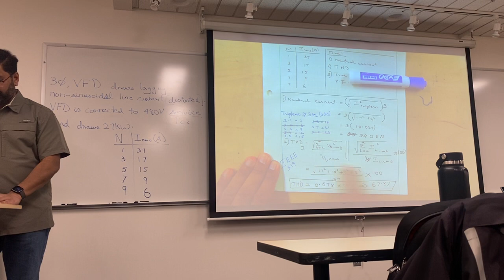This is true for both the voltage and the current, and this I picked up from the IEEE 519 standard. So I have 17 through 6, I take the square and then the square root of that, divided by 37, times 100: 67.8.